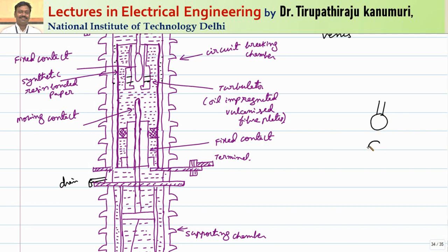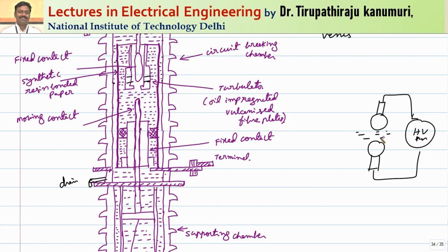Frequently we have to check the oil for dielectric strength using an oil tester. In the oil tester, two plates are connected to a high voltage supply with oil kept between them. The gap between the plates is maintained at 4 mm. For this 4 mm gap, the oil should be able to withstand 40 kV for one minute. If the oil can withstand 40 kV, the dielectric properties are proper; if not, the oil needs to be replaced.